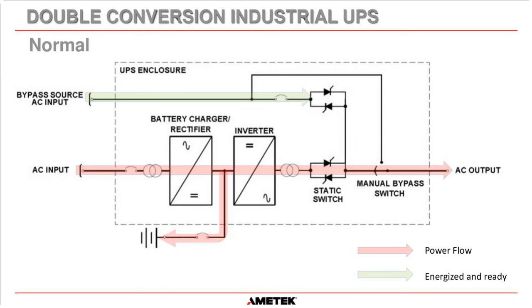And once again, I'm going to walk through the power flow for an industrial UPS. So in normal operation, 480 volts AC comes in, goes through the transformer, gets stepped down to a voltage within the system that is acceptable for the battery charger rectifier, and then that converts the AC into DC. And in this circumstance here, we have a 60 cell battery. So that means our float voltage is going to be 135 volts DC. Okay. So the batteries are kept charged by the charger, but the charger also supplies the current into the inverter. And we don't do any conversion. Remember on the last commercial UPS, this was boosted up to 650 volts. Here we stay at 135 volts into the inverter.